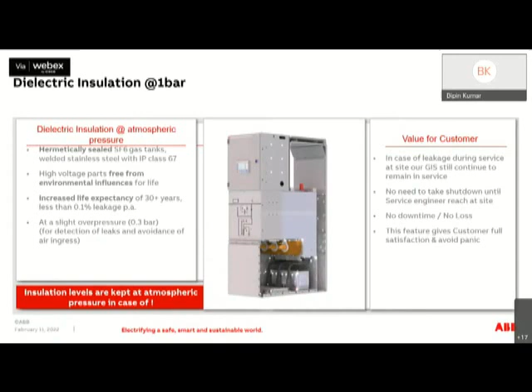Then we have this dielectric insulation at 1 bar, because our GIS are so designed that even if the SF6 leaks, you need not switch off the GIS. The GIS is very much capable to run at 1 bar pressure. That has been a feature of our gas insulated switchgear as a whole.